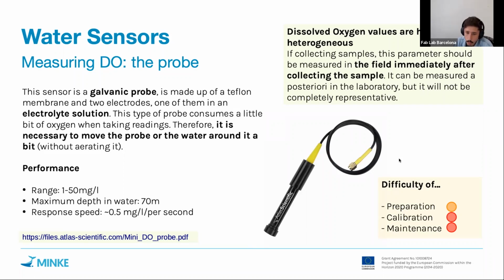The probe is measuring dissolved oxygen by reacting with the water. So stagnant water or non-moving water will not react properly with the probe, and you need to move the probe a little bit so that it reacts and provokes small currents around the sensor. We will see that the sensor depletes over time this capacity to react with the oxygen dissolved in water, and that is also very delicate. And we will see in the maintenance section how to take care of this. This sensor is not very complex to prepare, but it's a little complex to calibrate and to maintain. Don't be scared, because it's fine, but you will see that it takes a little time, and there are quite a few particularities for calibration and maintenance.